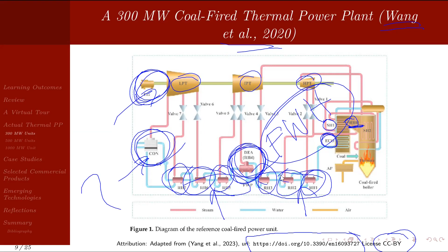So this is just to show you how the actual power plant cycle looks. And here you can see the operating conditions: the main steam temperature in this case is 538 degrees centigrade at full load, 100% load, and even at 75% load it's the same. Main steam pressure is 16.67 MPa for this 300 megawatt power plant, but at part load, say 75%, it's 13.25. Main steam flow rate is 260 kg per second.